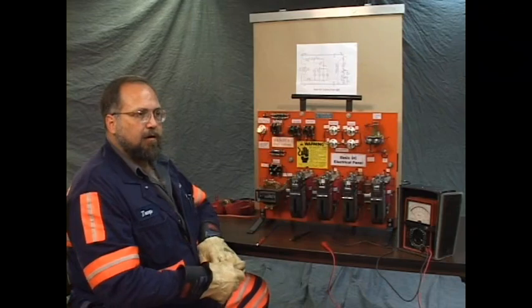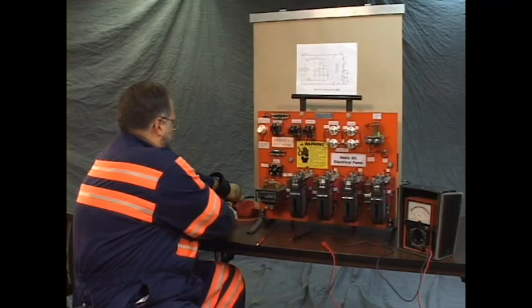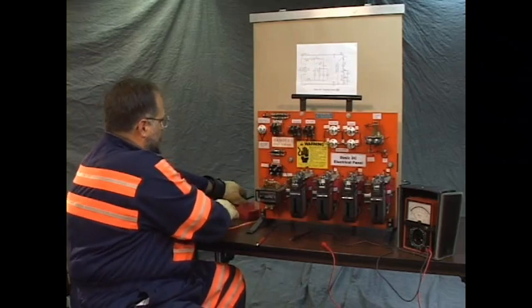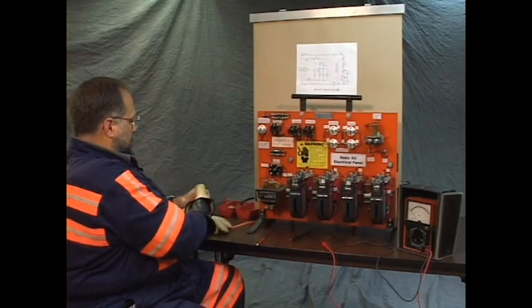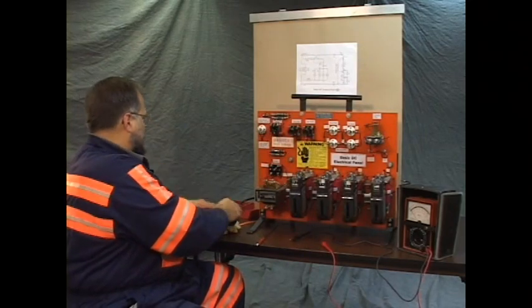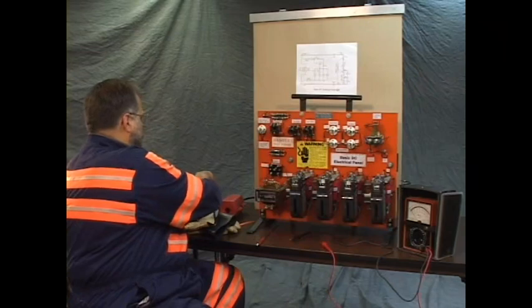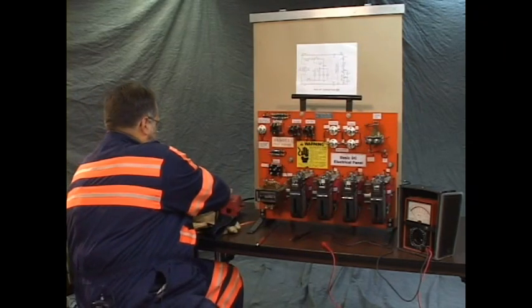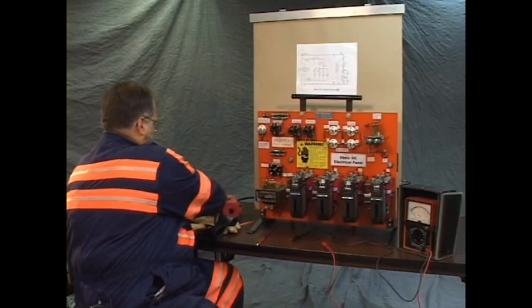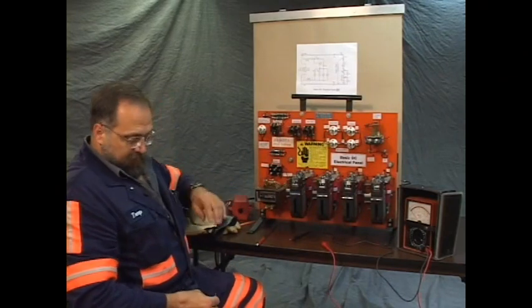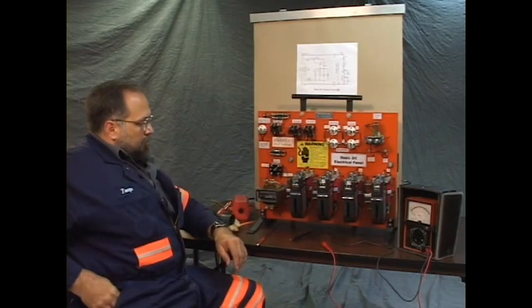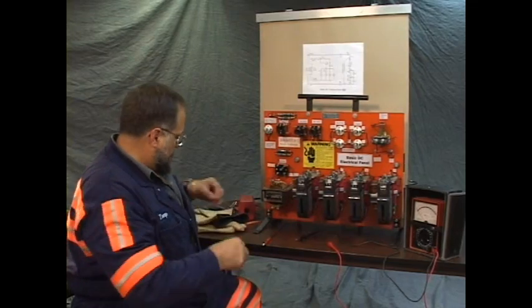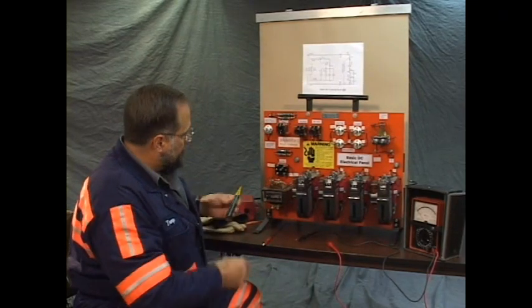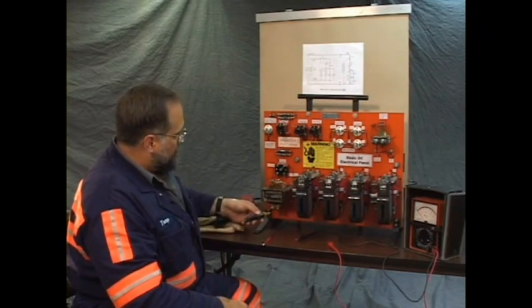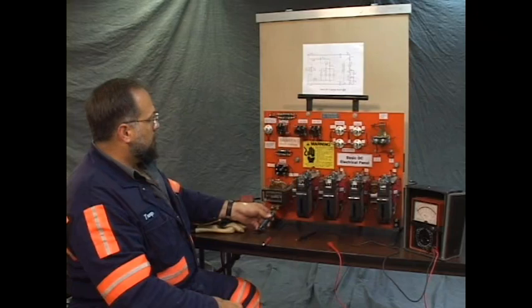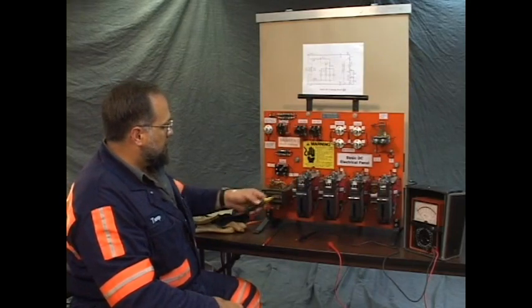So to start with, let's take the power off. We're going to de-energize the panel. Apply a lock and a tag to make the panel safe. I'm going to test this before I touch it using a tick tracer type tester. Note that the tick tracer type tester here won't detect DC, so I'm making my test for power on the AC portions.